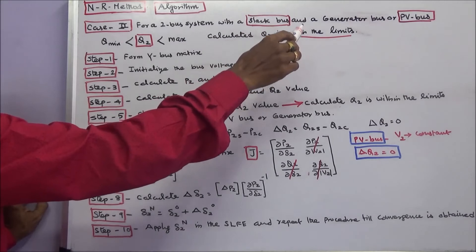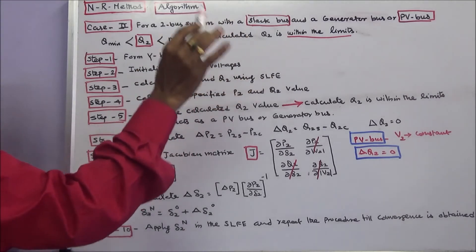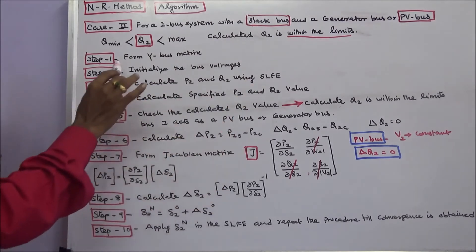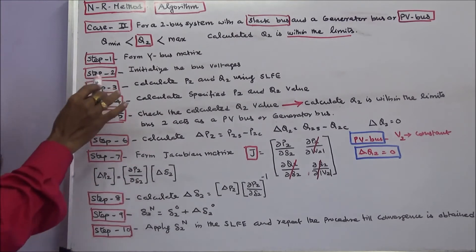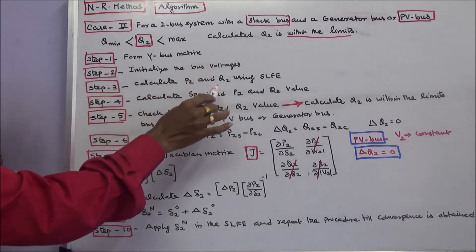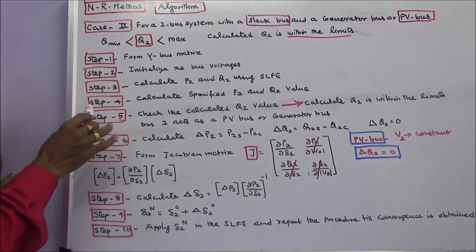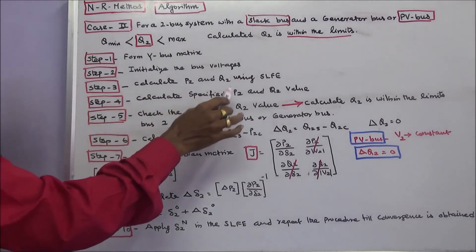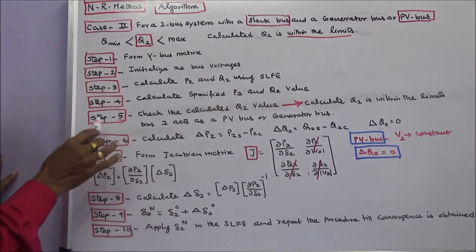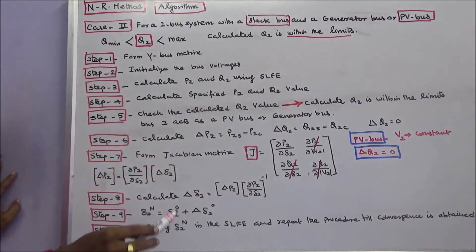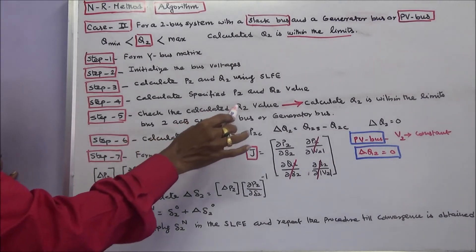Case 2: for a 2-bus system with a slack bus and a generator bus, or a PV bus. Here the reactive power limit is given. Case 2A: if the calculated reactive power is within the limits — Step 1: form the Y-bus matrix. Step 2: initialize the bus voltages. Step 3: calculate real power and reactive power using the static load flow equations. Step 4: calculate the specified real power and reactive power values. Step 5: check the calculated Q2 value. If calculated Q2 is within the limits, bus 2 acts as a PV bus or generator bus.